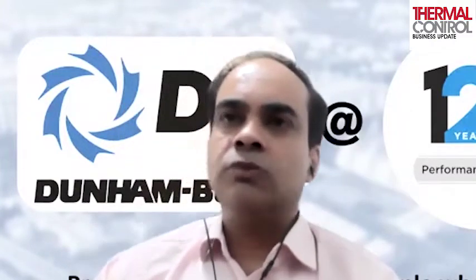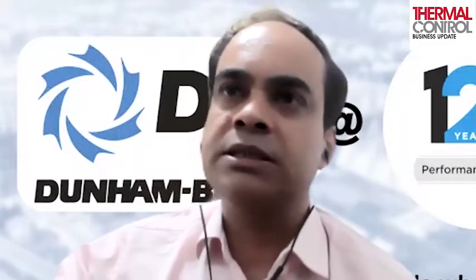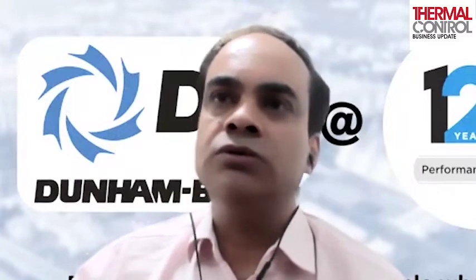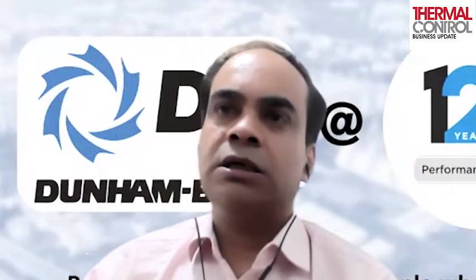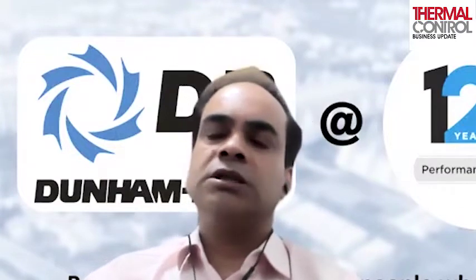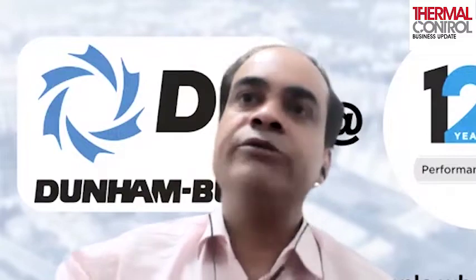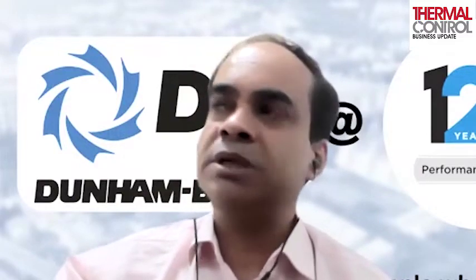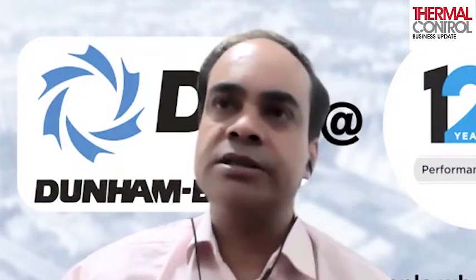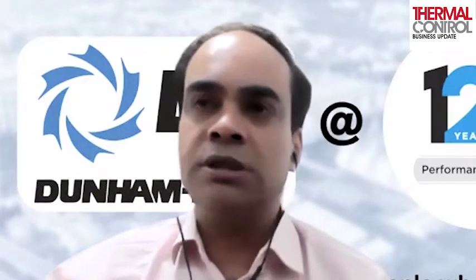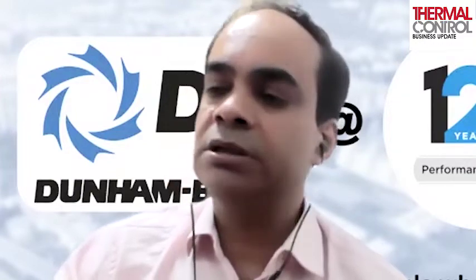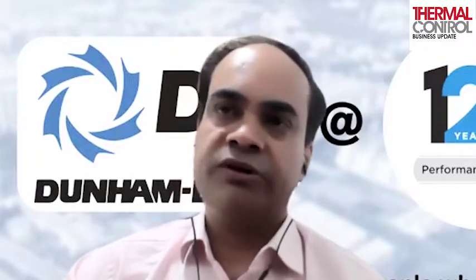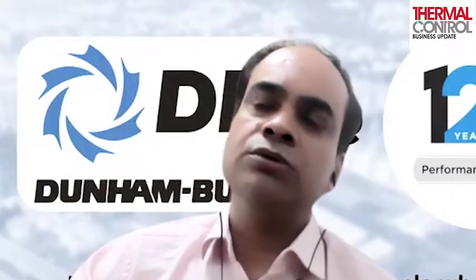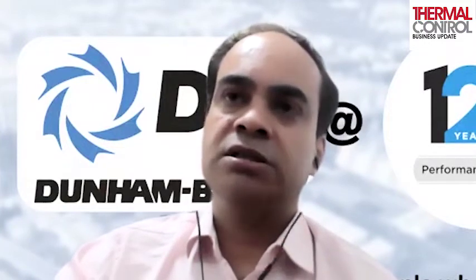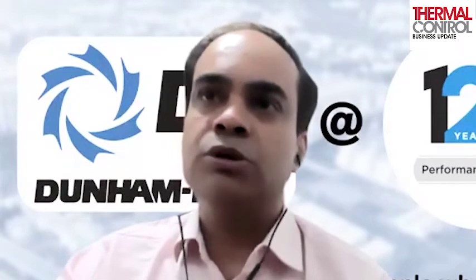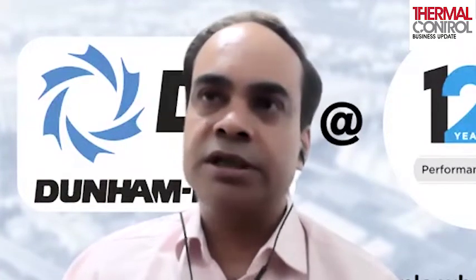My closing statement relates to the performance of the cooling tower on a sustainable basis. We need to adopt recent practices that ensure the cooling tower delivers in line with the promise made during design. So how do you ensure the cooling tower delivers the performance that was there on paper? Our most important criteria is measurement and verification. When you commission a plant, you need a proper measurement and verification process in place to ensure the cooling tower performs in line with the design consideration.